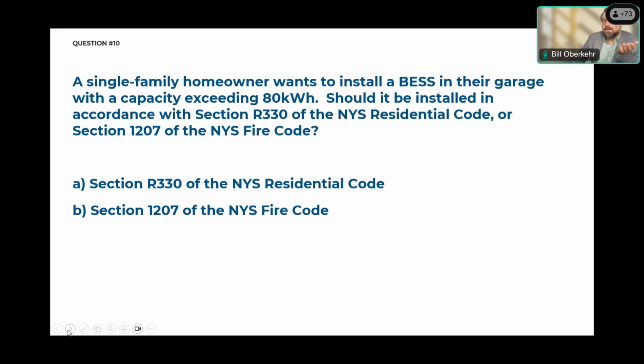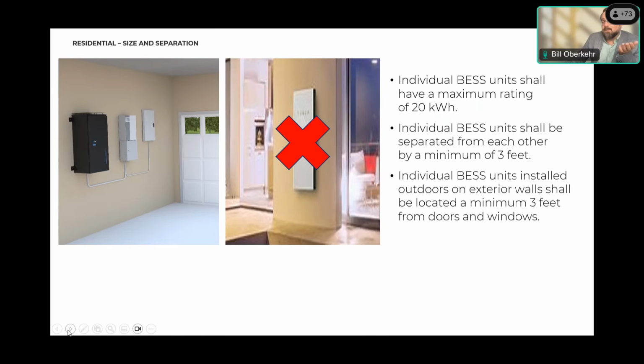One of the key differences between the residential code and the fire code is that the residential code has to deal with units that are capped at 20 kilowatt hours. One Tesla Powerwall, for example, is 13.7 kilowatt hours. So each unit has to be below 20, and then the aggregate capacity has to be below 40 or 80 kilowatt hours, depending on where the system is located. And they need to be separated by a minimum of 3 feet from each other.